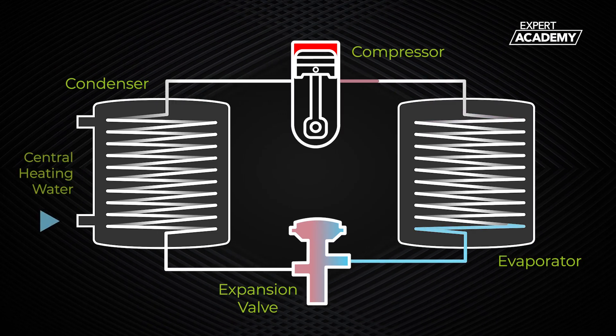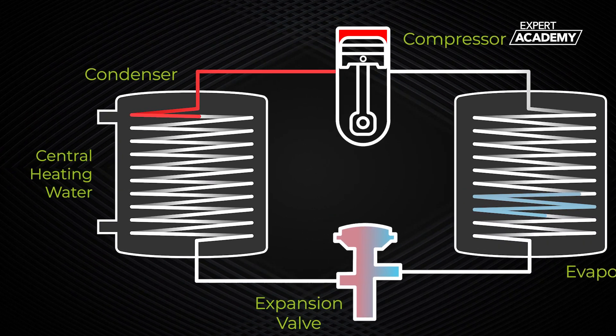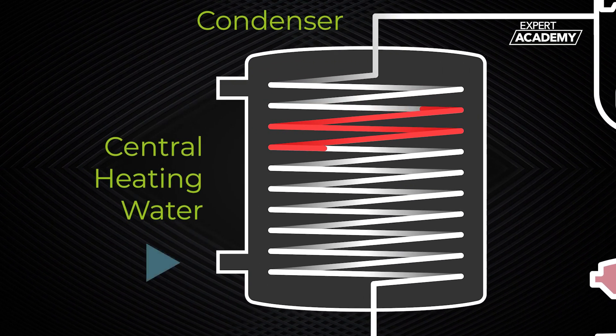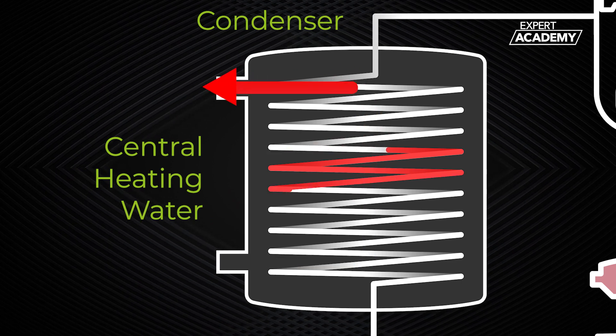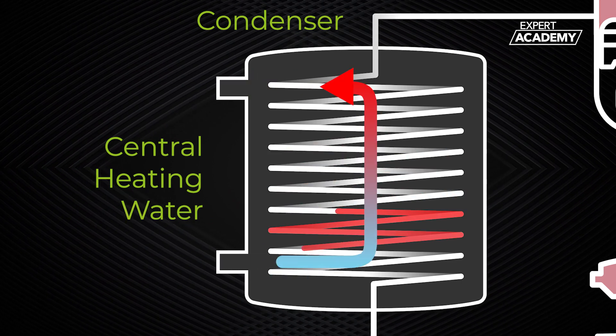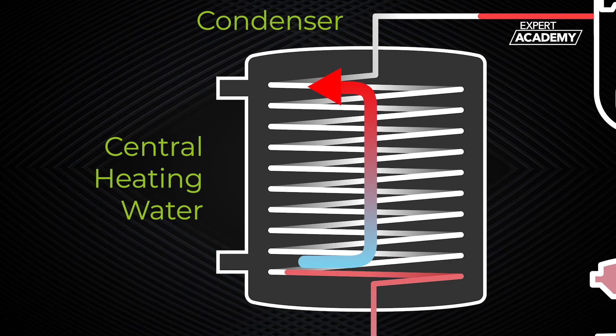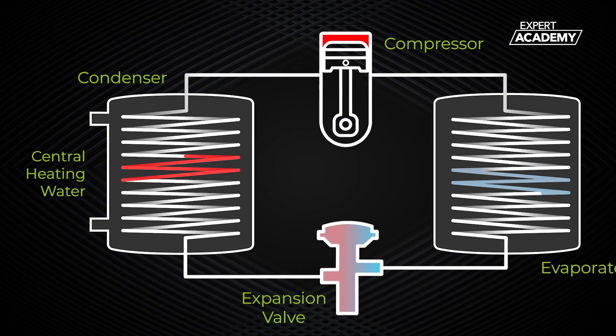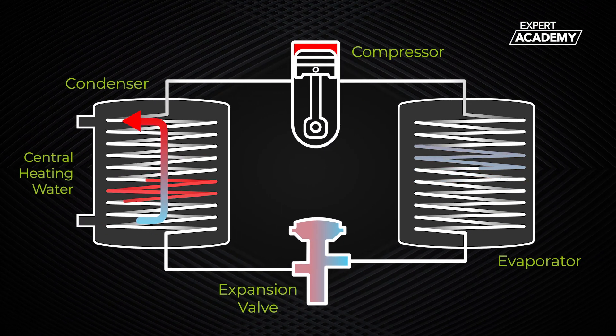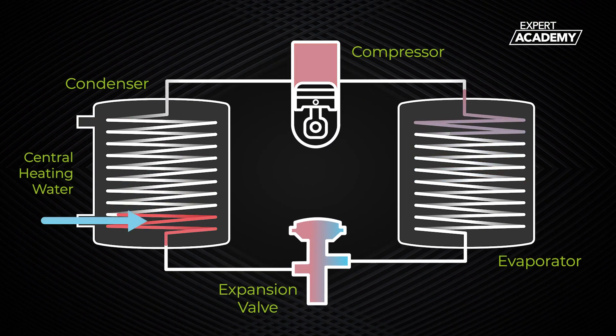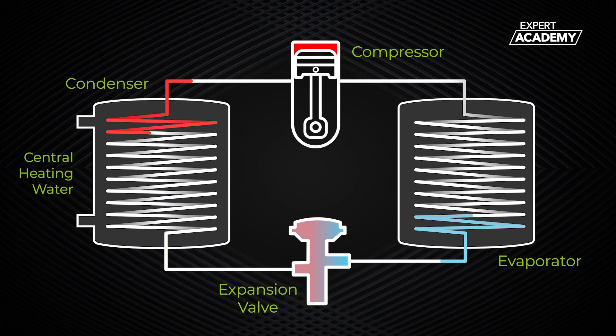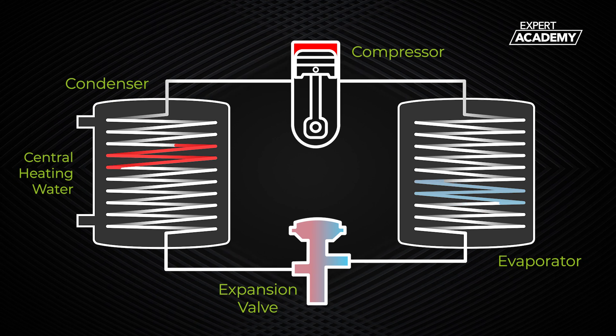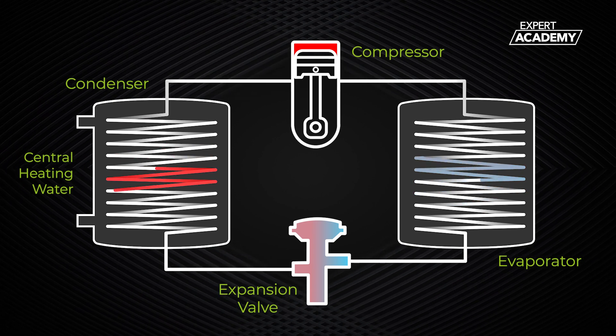We now have a condenser which is essentially a heat exchanger. It has a high temperature, high pressure vapor passing through one side with cooler central heating water passing the opposite way in the other side. As the vapor starts to transfer its heat into the central heating water, it begins to condense. Once it changes state from a vapor to a liquid, it will have released all the heat energy it previously absorbed into the central heating water, which will go around the heating system's pipes and radiators within the house, assisted by a circulator pump. We now have a relatively low temperature, high pressure liquid leaving the condenser.